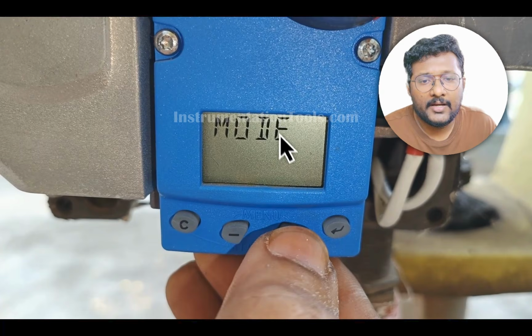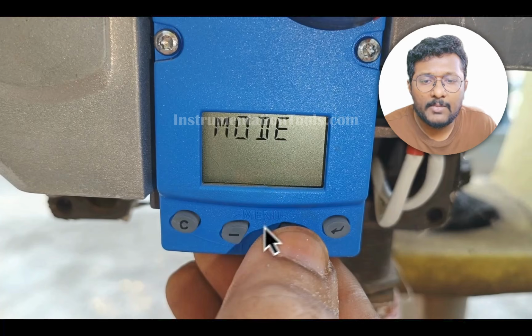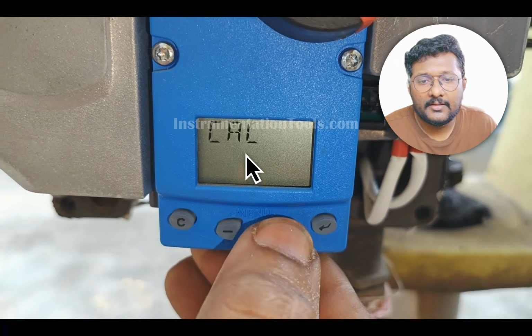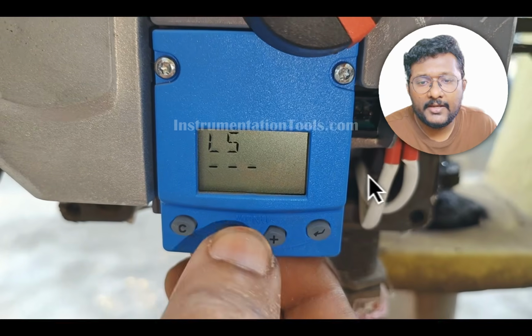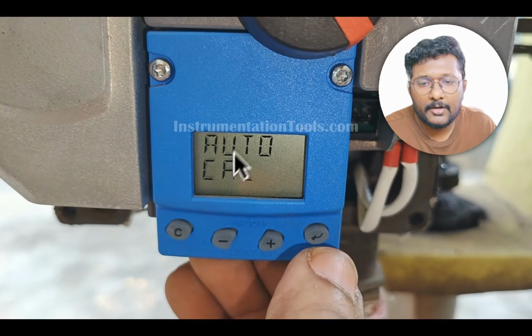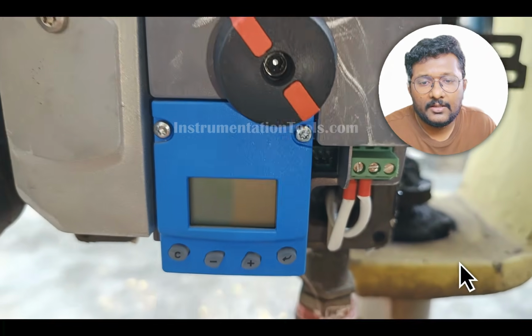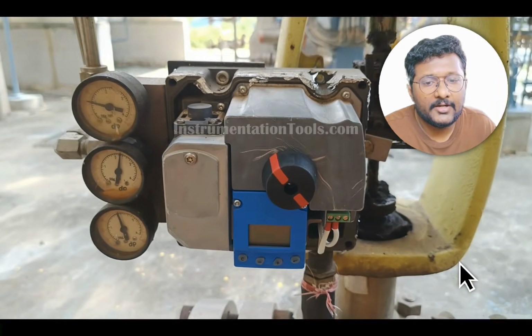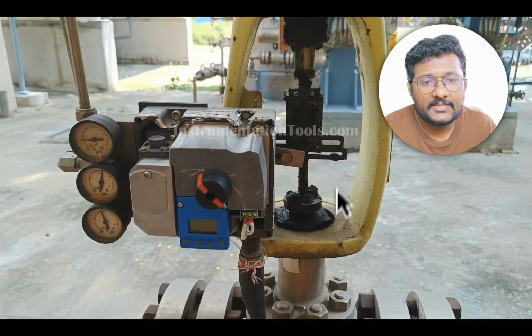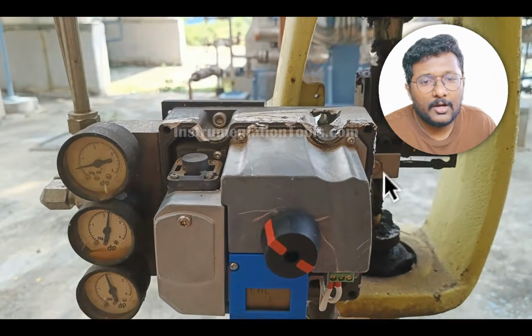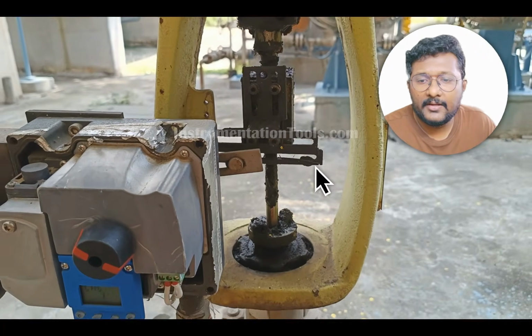See, now we are in mode and we can see the available options here by pressing minus or plus. I will press plus. See, parameter calibration. Okay, I need to go to calibration, enter, auto calibration, enter. That's it. The calibration is started. You can see the status here. The valve will automatically move the stem at the different points.